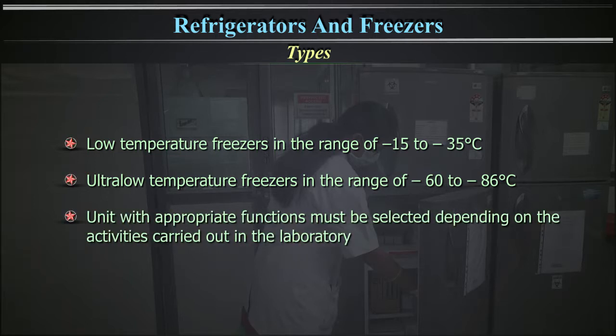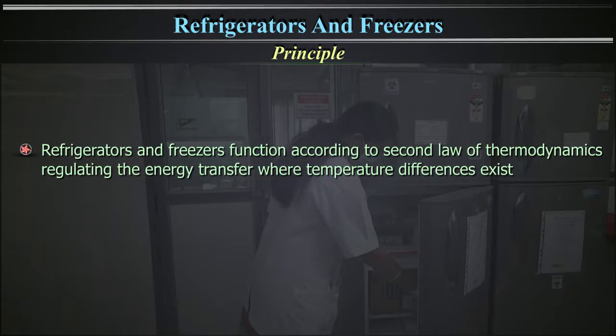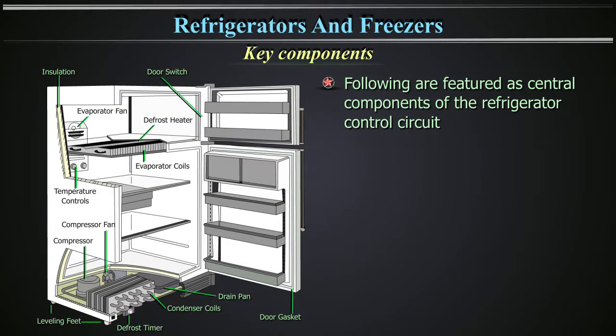A unit with appropriate functions must be selected depending on the activities carried out in the laboratory. Refrigerators and freezers function according to the second law of thermodynamics, regulating the energy transfer where temperature differences exist. Modern refrigerators and freezers are thermal systems which function mainly using a cycle called compression, where refrigerant gas with special properties achieving heat transference is used.